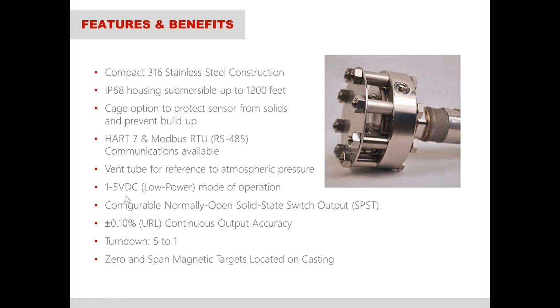So there's a question that we have. Would that not also allow for a lower level measurement due to a larger diaphragm or smaller span? So no, it wouldn't change the amount of span that you can achieve. You would still be limited by the actual sensor itself. You're correct that a larger diaphragm typically means that you can achieve lower pressures. However, the diaphragm of the actual pressure sensor is the same. We're just adding a diaphragm seal here.